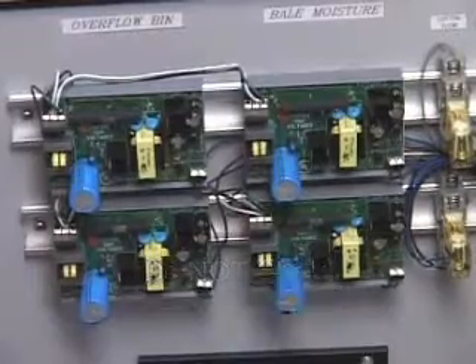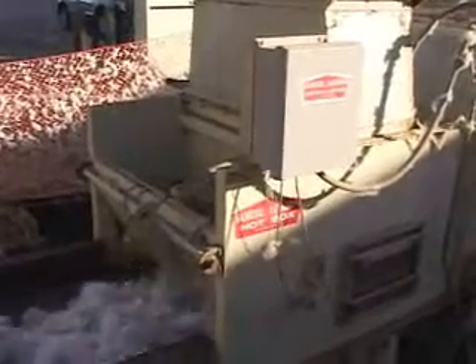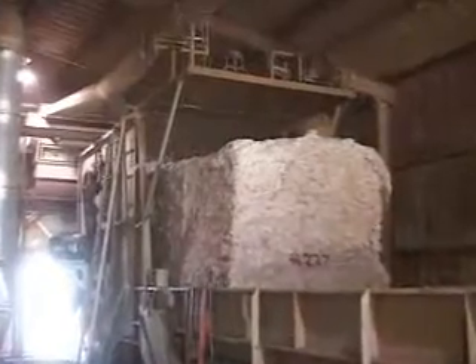The mirror is capable of accepting a signal for incoming moisture, moisture at the overflow, lint moisture, and up to 3 cotton flow signals. In addition to a wide assortment of Samuel Jackson sensors, the mirror is compatible with many other sensors on the market to give you maximum flexibility and choice. Let's take a look at a typical sensor installation.